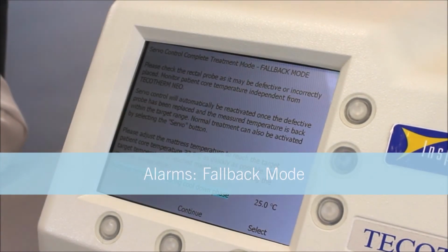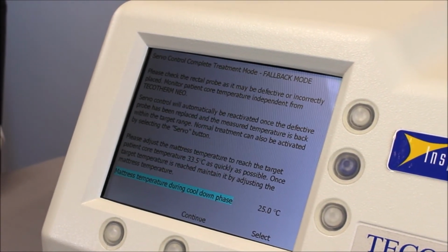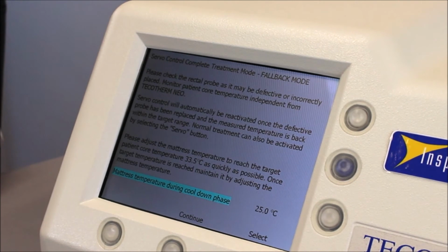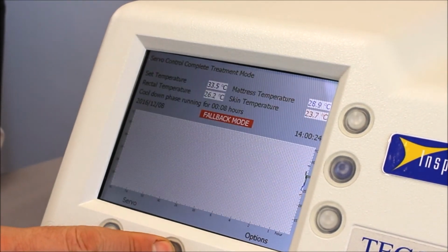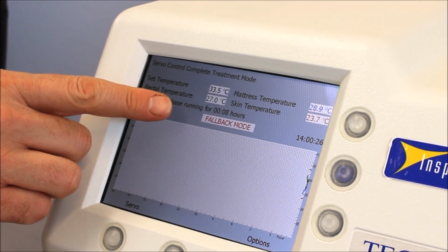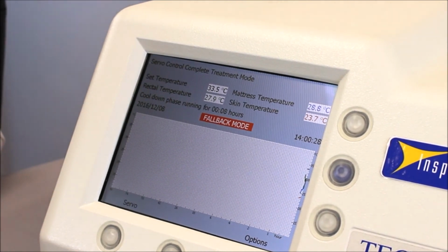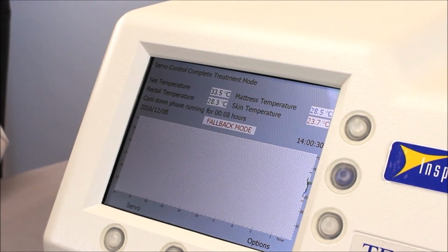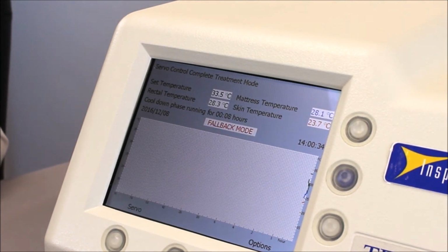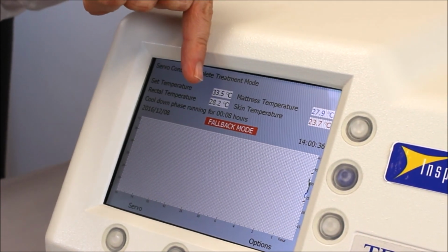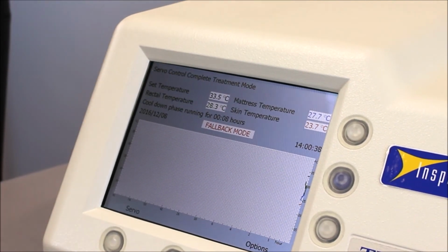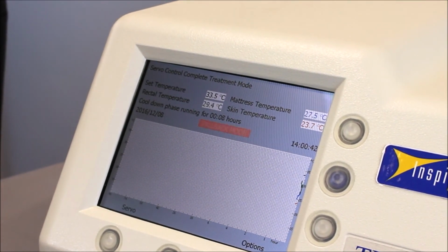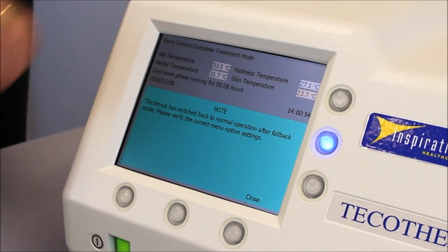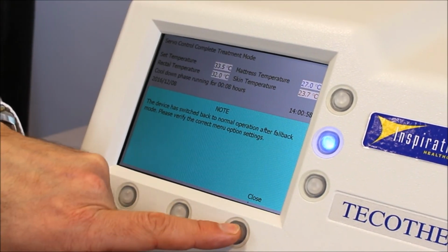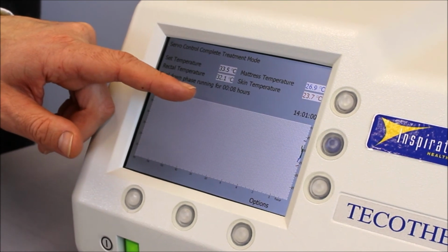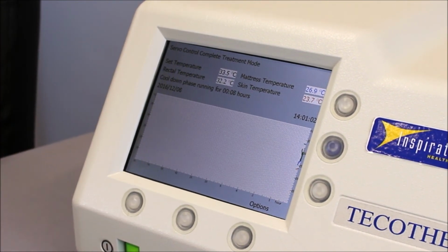If the probe falls out of the baby, it's quite likely that it will go into fallback mode. This is a safety mode whereby the mattress goes to a constant mattress temperature. If I press continue, we will see that fallback mode is alerted to us here. We need to then correct this problem by either changing the rectal probe or reinserting. Once we've done that and the temperature comes back above 29 or below 39, it will then continue to operate as normal. Now that we're back into range, I can press close, and I've lost the fallback mode alarm here, and we're back in treatment mode as we were.